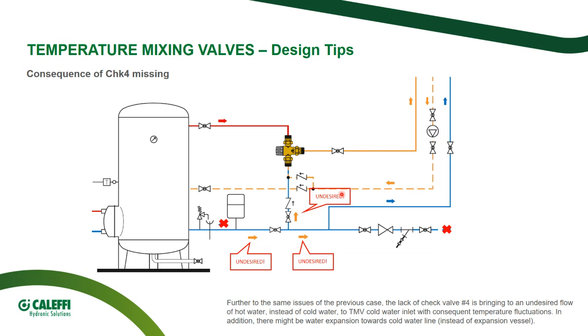Check valve number 4 protects the cold water inlet in the storage. If I forgot it, I might have backflow of hot water and recirculated water towards the cold water line, towards the distribution network and towards my valve. So my mixing valve will receive hot water and hot water too.